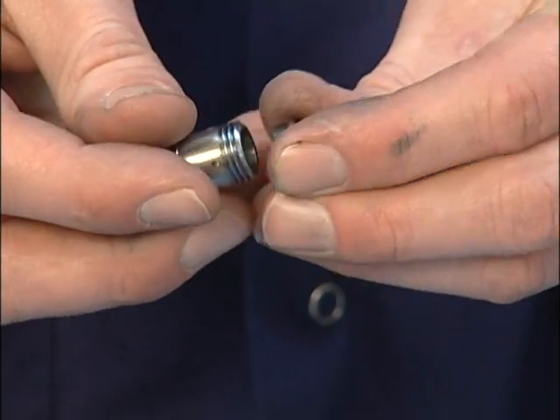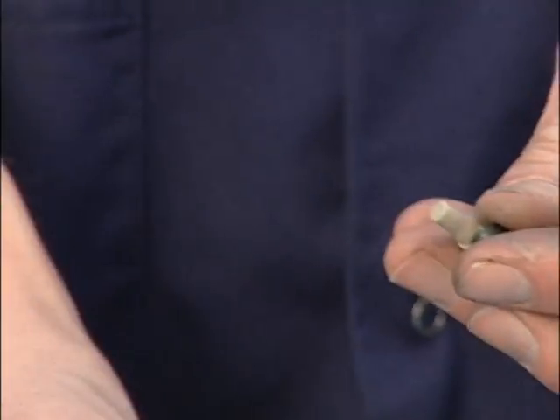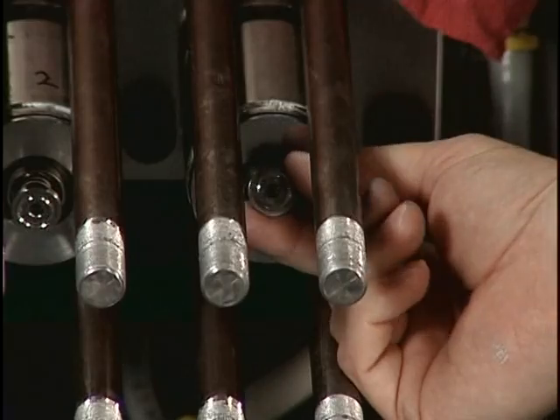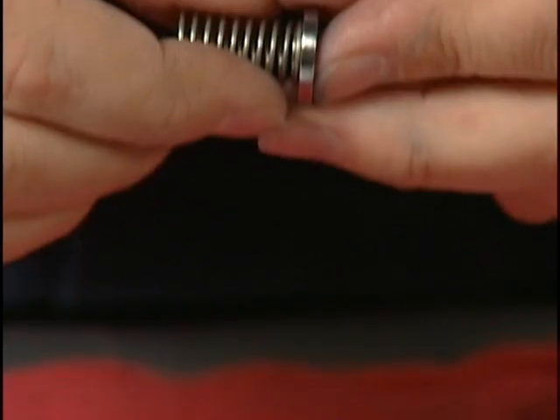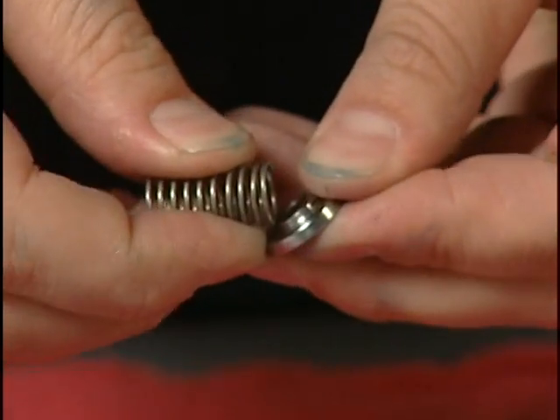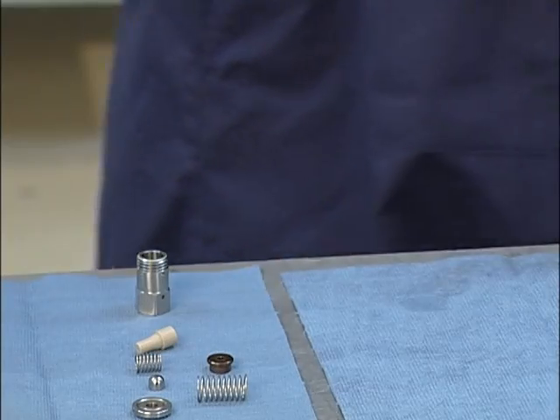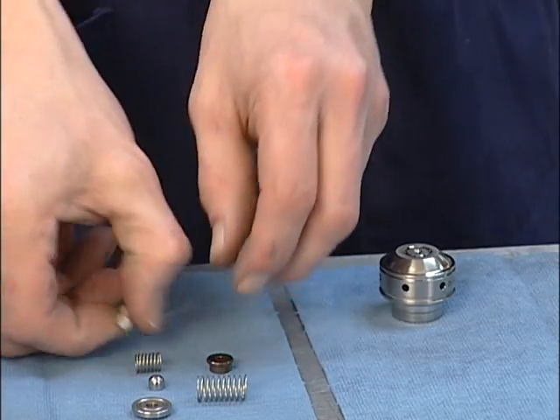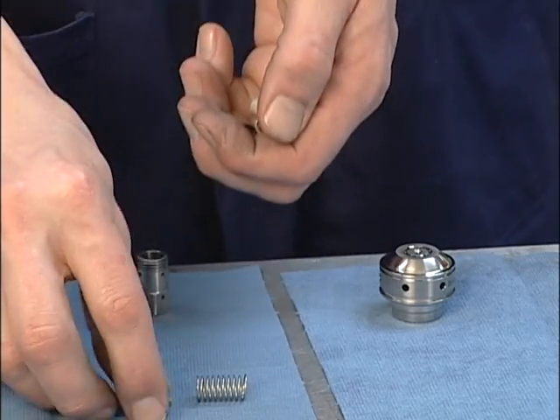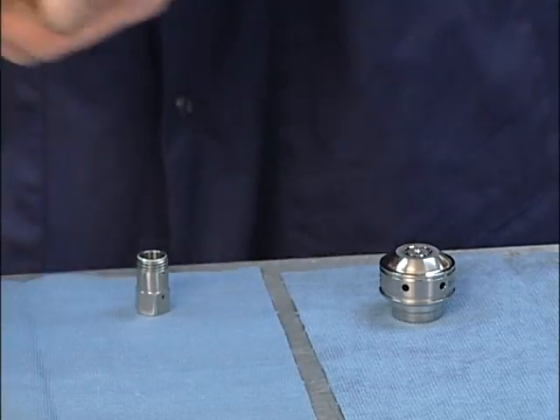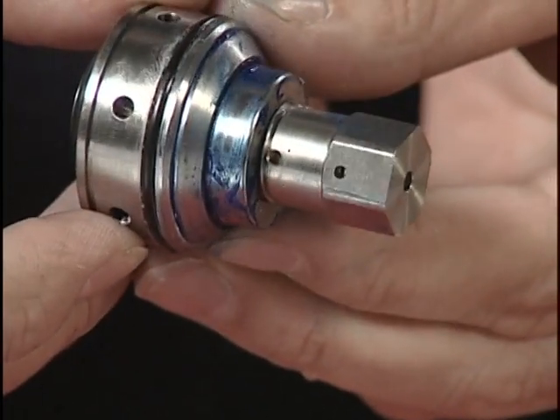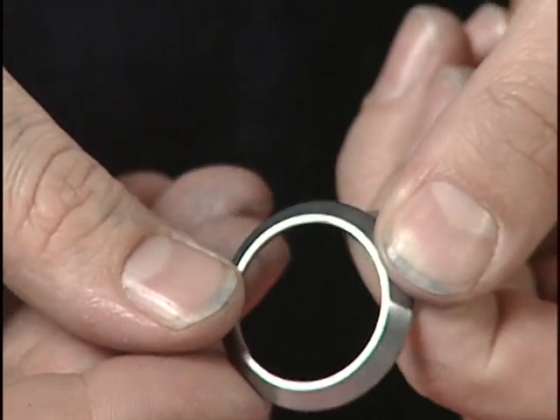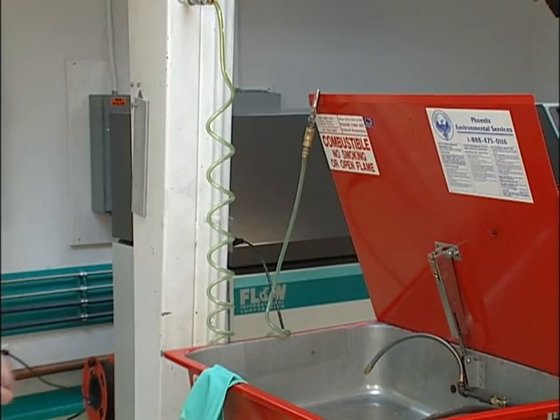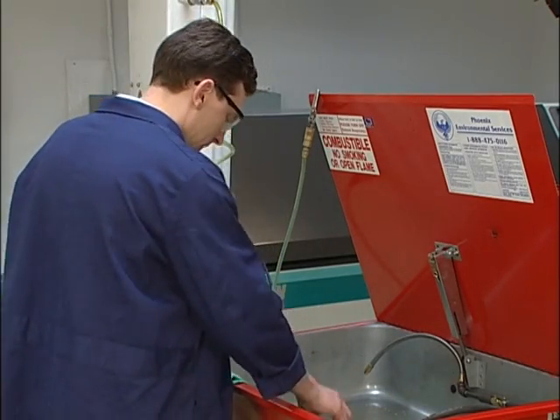Remove the compression spring, outlet poppet assembly, and outlet seat. Remove the inlet poppet from the high pressure cylinder and then remove the inlet poppet retaining spring. Discard the inlet poppet, poppet guide and seat. The end cap static seal may be compressed onto the check valve body. Do not attempt to remove it unless it shows signs of damage or leaking. Clean all the check valve parts with solvent and compressed air.